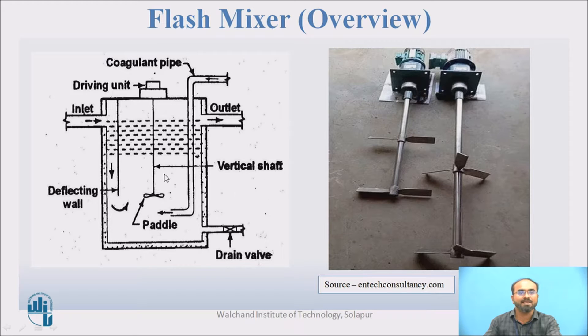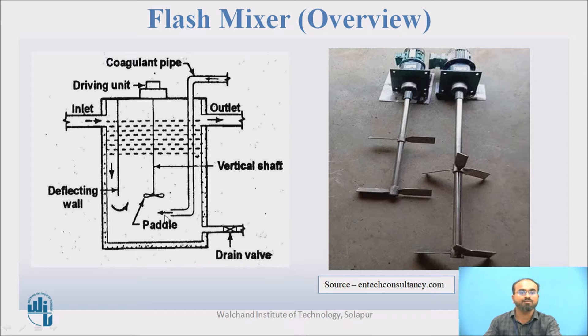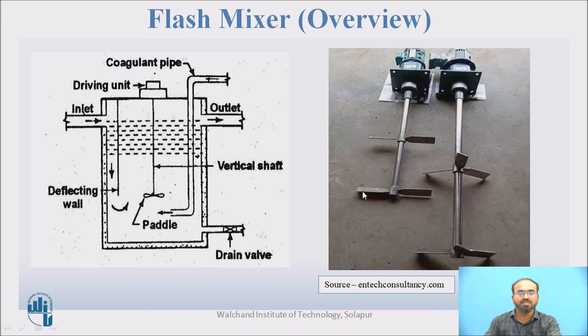This is a typical diagram of a flash mixer where you can see paddles provided for flash mixing. The inlet is always from the top part, and there is a deflecting wall so that water passes through, entering the tank from the bottom side and coming out to join the outlet. The dose being added is always added near the paddle — at the bottom of the paddle. Impurities that settle due to higher density than water can be removed through the drain. The paddles, which we typically design, involve determining their diameter, shape, and size.